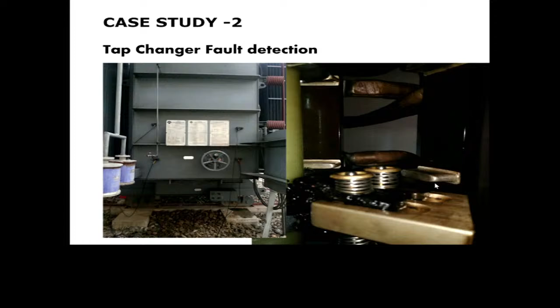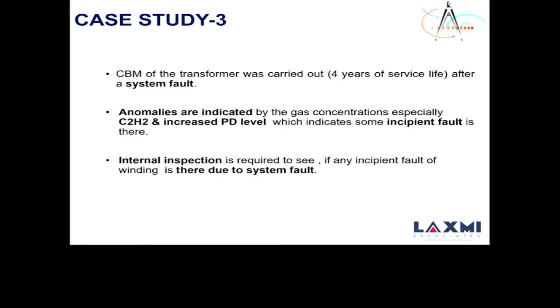Then you have tap changer fault detection here. What you are seeing is a DGA pattern. DGA is high after 3 months, then PD signals are very high here. After locating the partial discharge by acoustic sensors, we opened that area and found carbonation in the OLTC contact, and that was rectified on-site.